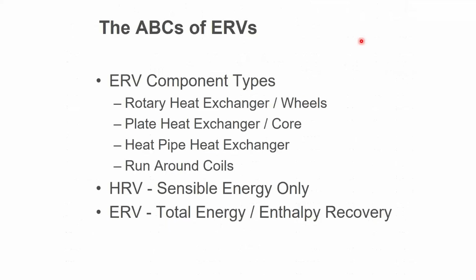There are different kinds of heat exchangers that we can have in the ERV. Wheels are pretty common, as are fixed plate cores. Heat pipes and run-around coils are not that common. There are numerous reasons for that, one of which is they don't comply with energy code. Not that they don't save energy, they certainly do. They don't comply with the energy code, though.